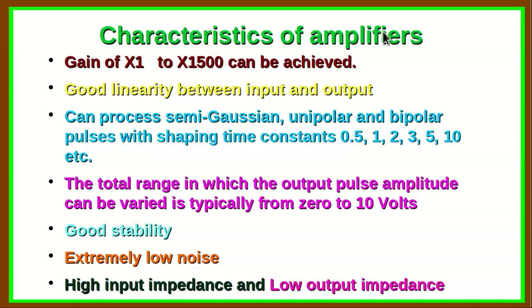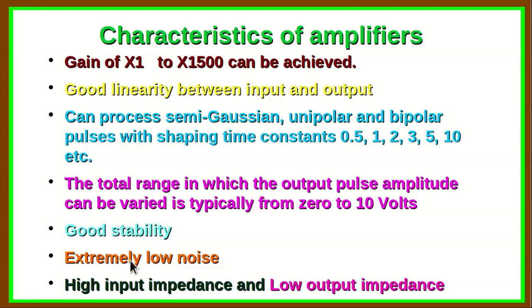Important amplifier characteristics: the gain should be variable from unity to about 1500, controlled via a coarse control and a fine control. There should be good linearity between input and output, with the ability to process semi-Gaussian unipolar and bipolar pulses with shaping time constants varying from 0.5 microseconds to 10 microseconds. The output pulse amplitude range is typically 0 to 10 volts, though sometimes 0–5 V or 0–2 V. Good overall stability of the amplifier gain and low noise are essential, with high input impedance and low output impedance.